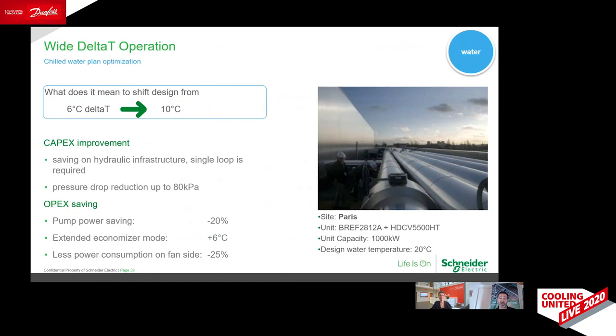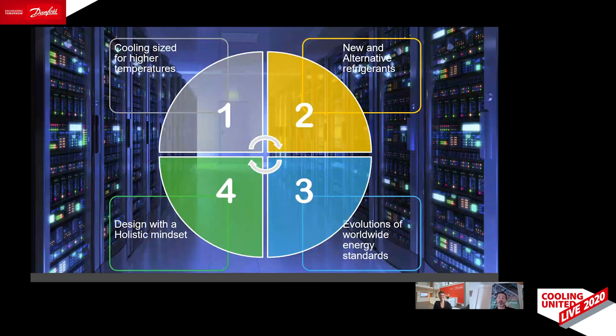One of the trends is to use wide delta T, to move from the traditional 7-12 or 6 degrees Celsius delta T on the inlet and outlet temperature to much more, to 10 or 12. This certainly impacts the air conditioning unit, but it reduces the pipework, it reduces the pump power, it reduces the pressure drop of the system. So at the end of the day, the overall figures show that the data center is more efficient, less expensive, and the overall holistic view is much better than thinking only about the small portion of each of the components.